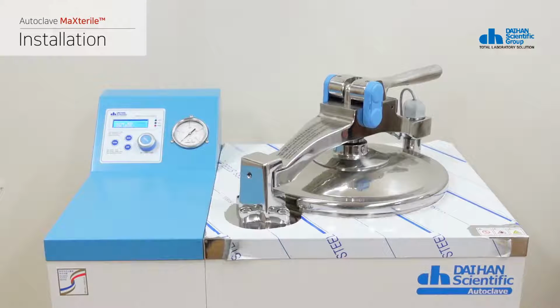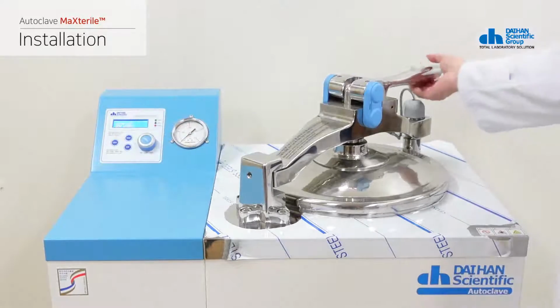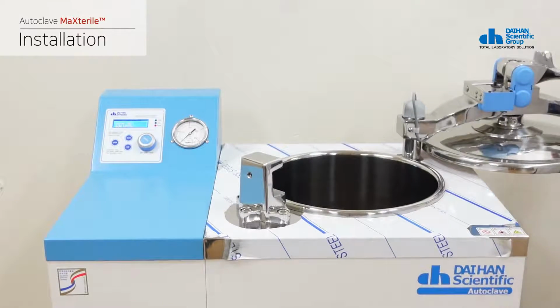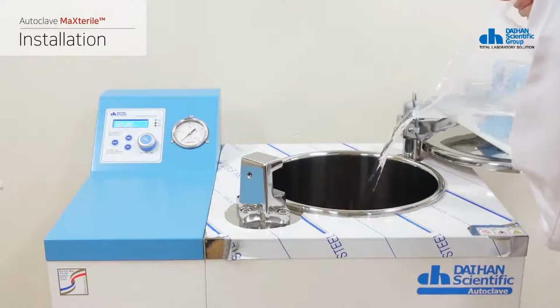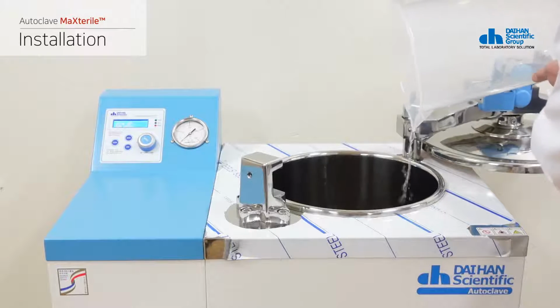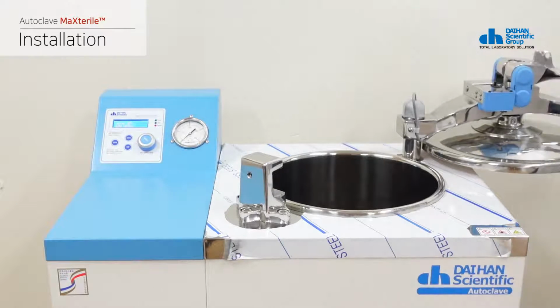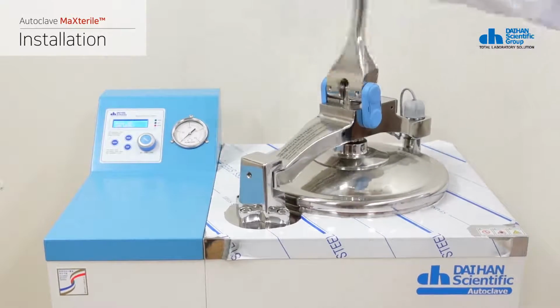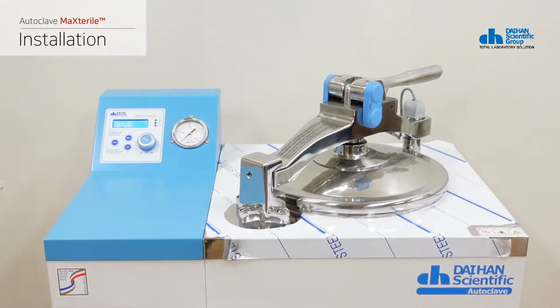If there is not enough water in the autoclave, error 3 low-level error occurs on the operation screen, and a warning beep sounds after about 1 minute. If there is not enough water in the autoclave, press the door open button to open the door, and then fill the chamber with distilled water to the heater cover. Turn the power off and on again to clear the water shortage error.